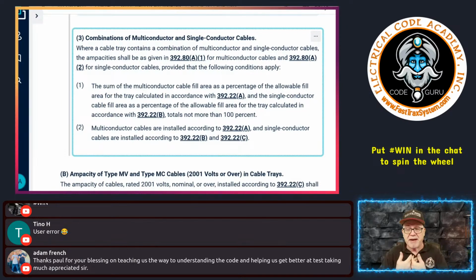But as far as ampacities go, you calculate the single insulated conductors just like we did, separately from the multi-conductor cables. You do them separately, okay? And that's all it says to do. See, that's what it says right here.